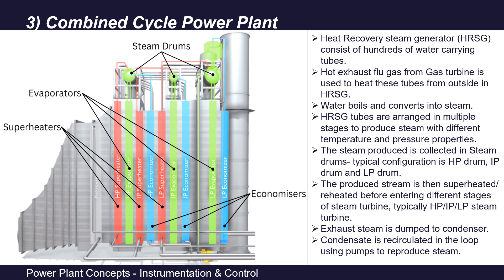The exhaust steam, after rotating the turbine blades, is cooled to condensate form. This condensate is collected in the condenser and recirculated in the loop again using pumps to produce steam. It is essentially a closed cycle — water enters the system once, is heated to produce steam, that steam rotates the turbine blades connected to the rotor shaft producing electricity, the exhaust steam is condensed, collected in the condenser, and pumped back to the drums. Any losses due to leakage are compensated by demineralized water.